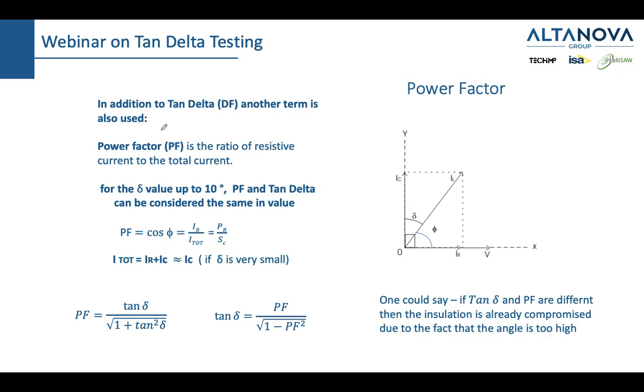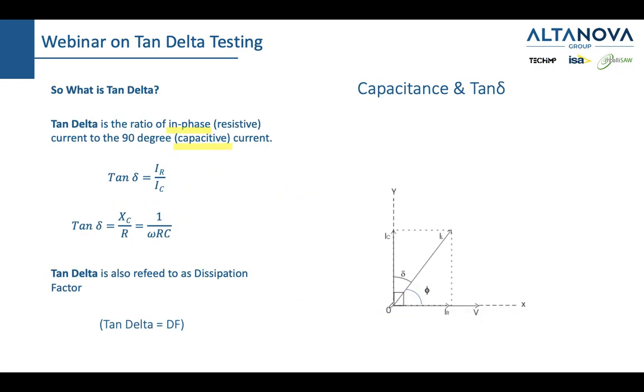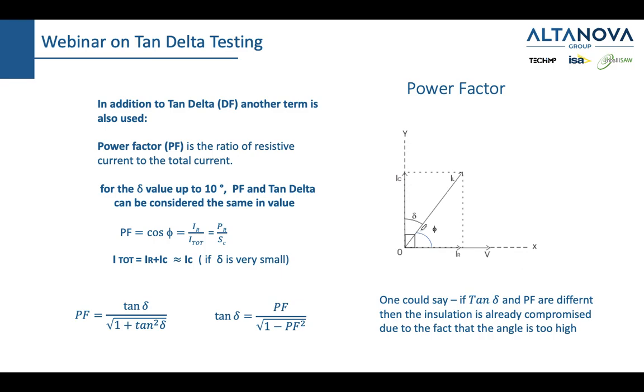They're very similar because, you see, tan delta is resistive current over capacitive current, while power factor is resistive current over total current. And since we said that this angle is very small, let's say this would be your total current, whether I'm dividing this length with this length here, IC, or this length with this length here, the yellow line, it wouldn't make much difference. So one could say also that power factor is cosine phi, while phi would be this angle here, or IR divided by I total. And of course, there are formulas which can convert one into the other, so this one and this one.